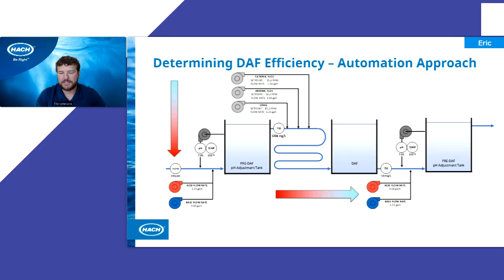You can also measure that TSS on the back end, on the effluent of that DAF tank. So now we can do a feed forward and a feed back control to really optimize that chemical dosing. And then, of course, if you have another DAF running in series, that would be where you could do some more pH adjustments. So this is just a snapshot of how we would automate that process to get real control of our effluent and chemical dosing.